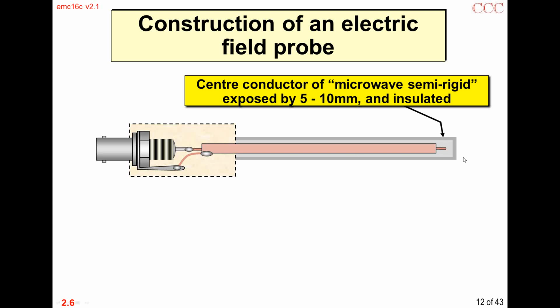So we tend to make these fairly short, because one of the points about close field probing is that the probes aren't very sensitive. We don't want them to be sensitive because we want to be able to use them outside of a shielded room on our ordinary test benches. If they're sensitive, they pick up what's going on in the environment, and we don't really want that.